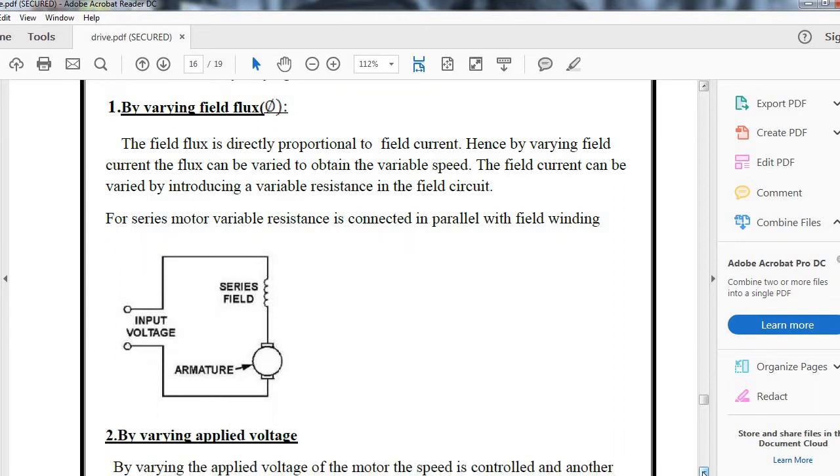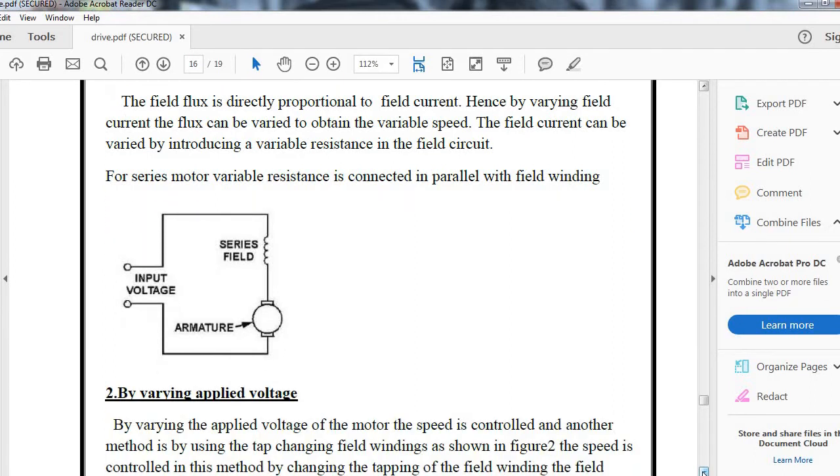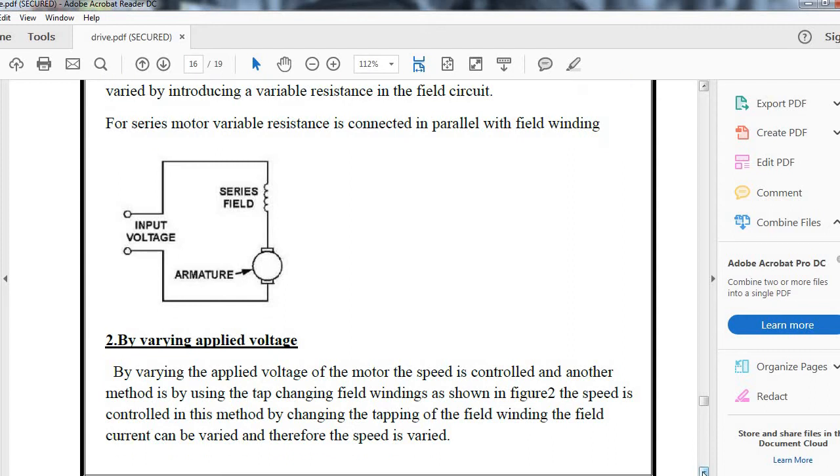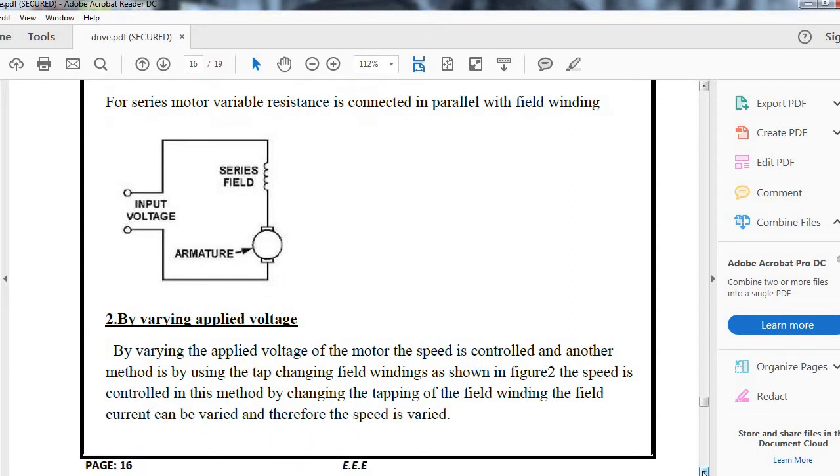Second is by varying the applied voltage. By varying the applied voltage of the motor, the speed is controlled. Another method uses tap changing of the field winding as shown in figure 2. By changing the tappings of the field winding, the flux generation and field current can be varied, therefore speed is varied.